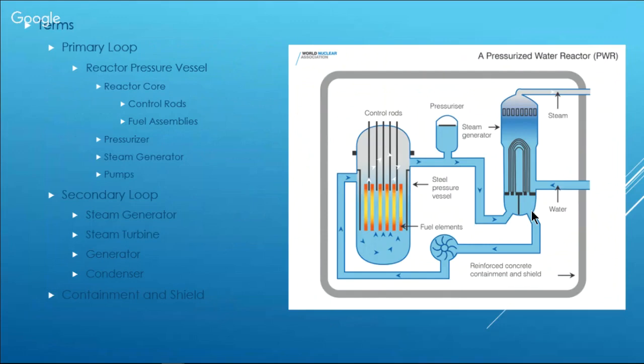So this water gets denser. Now you have it pumped into the reactor. If the water's denser, the water molecules are closer together, so the neutrons have a shorter mean free path, and therefore it takes fewer interactions and less time to become moderated. That means you have more thermal neutrons in the reactor core at that time. More neutrons are going to be absorbed by the fuel, based upon the six-factor formula, that K effective, which means more fissions take place. You have more fissions, you have more heat generated, correct? The water heats up and this T hot will get warmer too. So what you end up having is this equalized here. Your T average stays the same, because this goes down 10 degrees, this goes up 10 degrees, and your T average is the same.